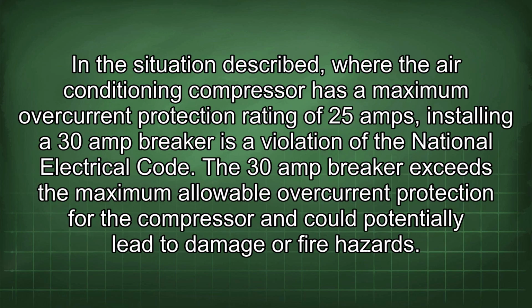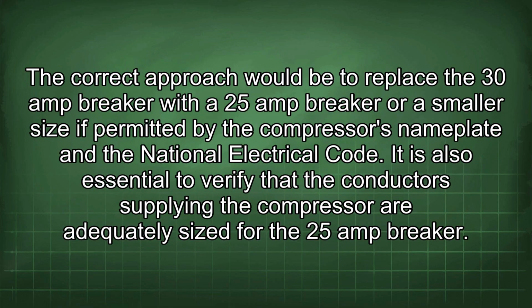In the situation described, where the air conditioning compressor has a maximum overcurrent protection rating of 25 amps, installing a 30 amp breaker is a violation of the National Electrical Code. The 30 amp breaker exceeds the maximum allowable overcurrent protection for the compressor and could potentially lead to damage or fire hazards. The correct approach would be to replace the 30 amp breaker with a 25 amp breaker or a smaller size if permitted by the compressor's nameplate and the National Electrical Code.